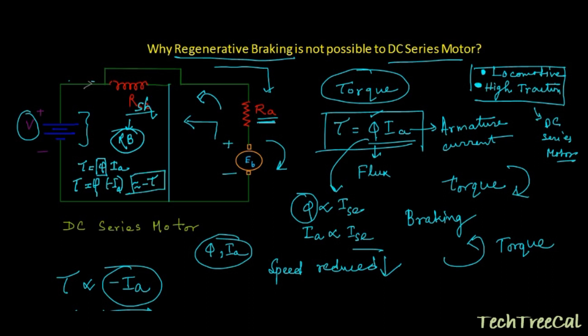With the flux constant and Ia reversed, the torque becomes negative, helping to reduce the speed of the motor and creating braking. This explains the constraints of using a DC series motor for regenerative braking and how changing it to a shunt or separately excited motor — using a power contactor or other means — allows regenerative braking in DC motors.